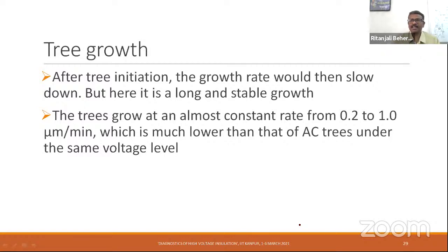If we compare the tree progress, in one report the applied DC voltage was about 50 kV, whereas this situation is more or less similar to AC voltage at 15 kV. So 50 kV and 15 kV is the level of stress with which we compare and try to understand the treeing progression.